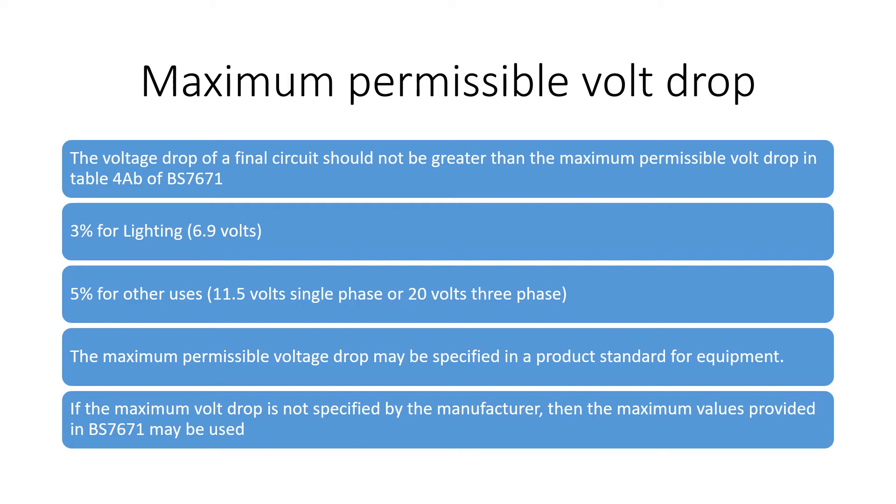One thing to bear in mind is that if the equipment being supplied is subject to a product standard, the voltage at the load must not be lower than that specified in the product standard. So it's important that we always check the product standard and manufacturer's instructions for any specific equipment.